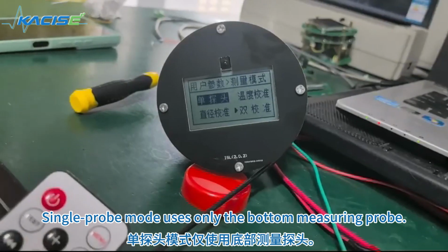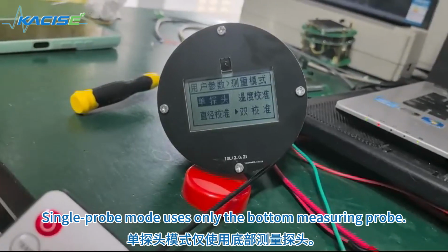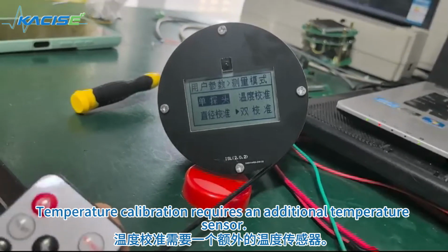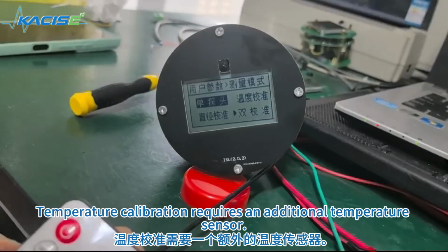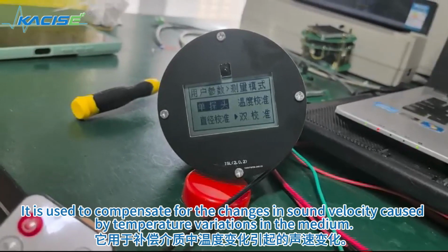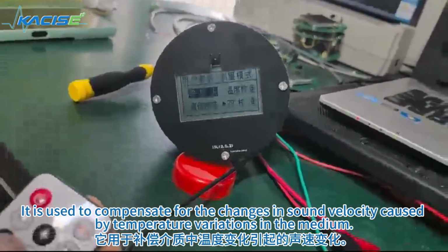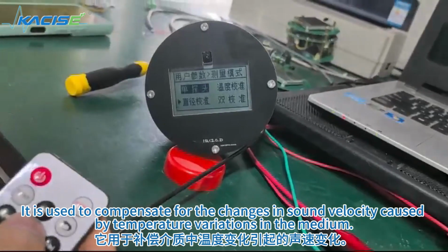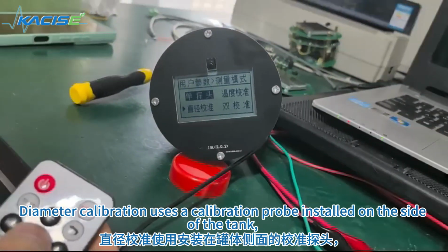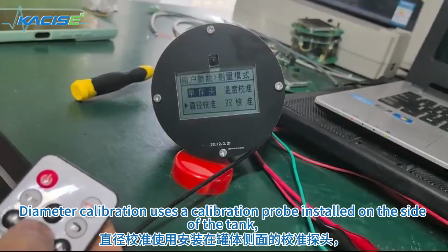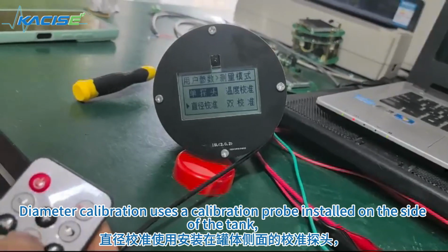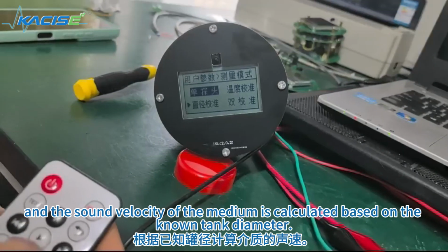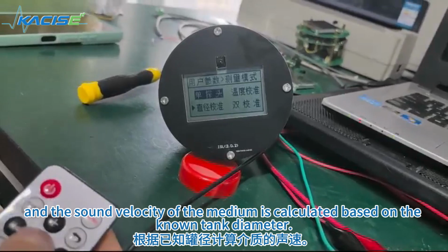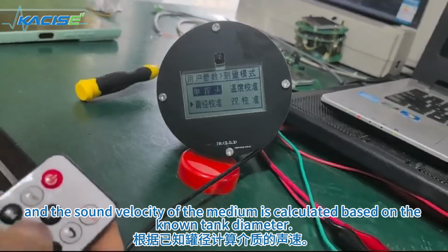Single probe mode uses only the bottom measuring probe. Temperature calibration requires an additional temperature sensor. It is used to compensate for the changes in sound velocity caused by temperature variations in the medium. Diameter calibration uses a calibration probe installed on the side of the tank, and the sound velocity of the medium is calculated based on the known tank diameter.